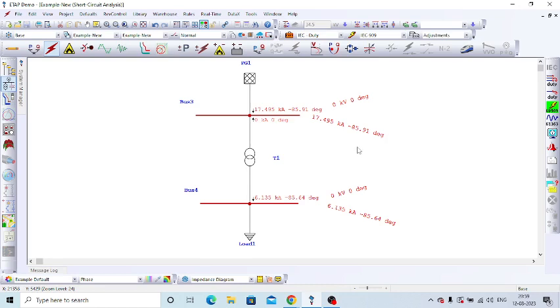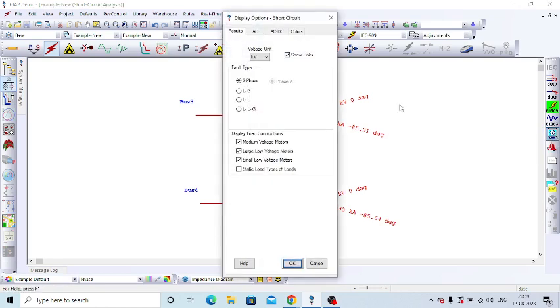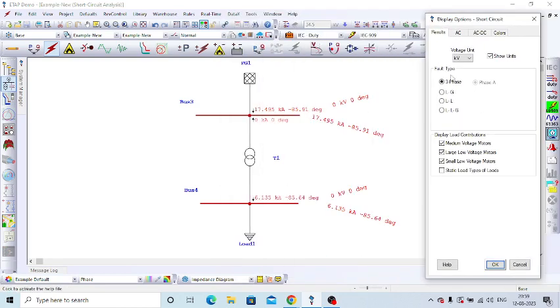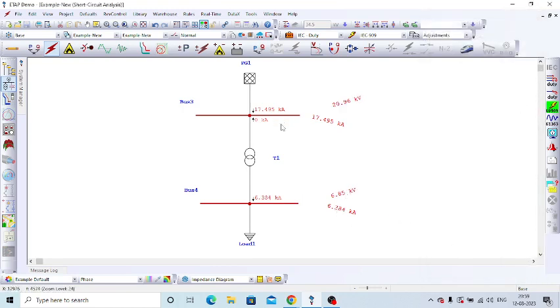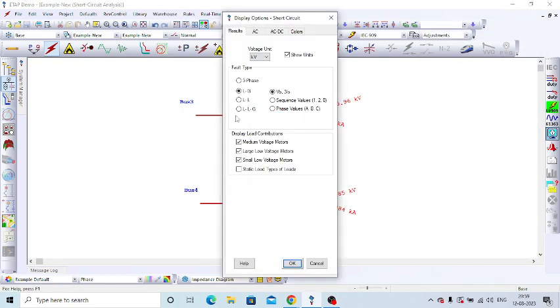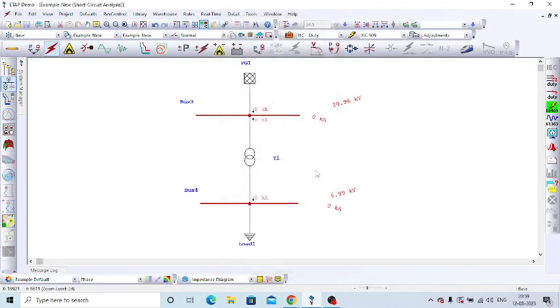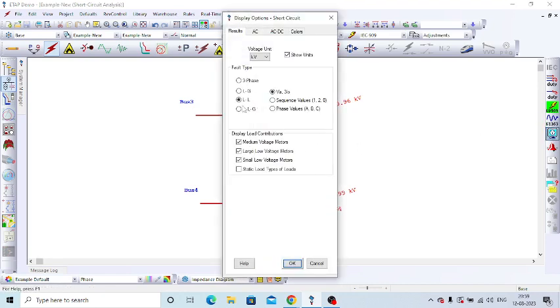So as we know, we have different types of fault: three-phase fault, single line to ground fault, double line to ground fault, and line to line fault. So what fault current it is, we can check through this display option. So presently it is three-phase fault. Suppose if you want single line to ground fault, we have to go with single line to ground fault, and we can see the single line to ground fault value here. So for the line to line, then LLG.